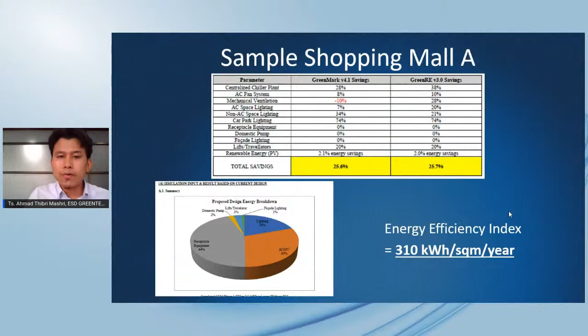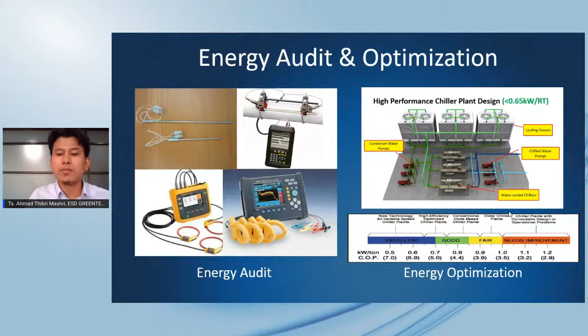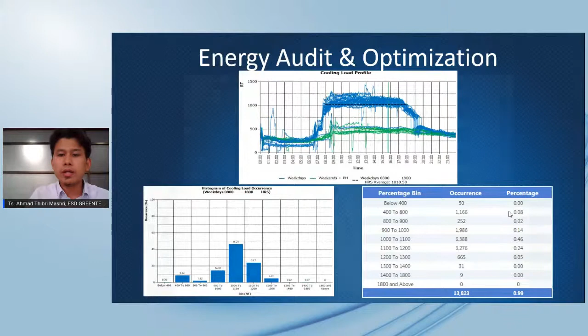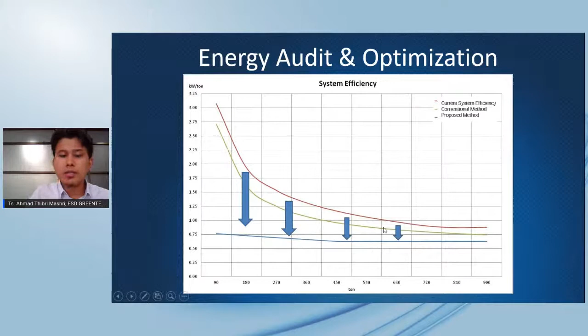Okay, for an existing building, unlike a new building, since the building is already up and running, we don't have to model or simulate anything, but instead we can conduct an energy audit at the actual live building. So from the audit we will get all the data, all the important profiles, all the relevant histograms on the cooling load occurrence, and from there we can design our system efficiently to ensure that good kilowatt per ton is met at all load conditions, unlike a conventional system where at full load maybe it operates better, but at low load it doesn't meet the requirement. Okay, this is just a sample of an energy audit project where we show improvement to the building.